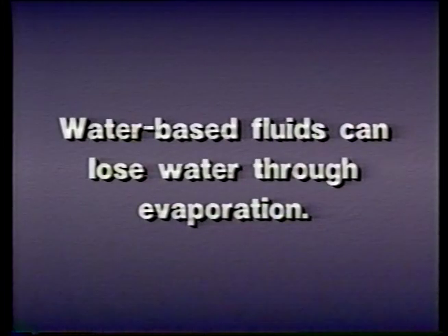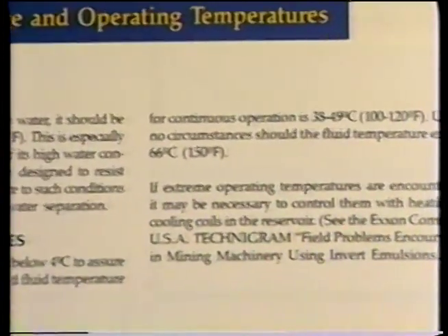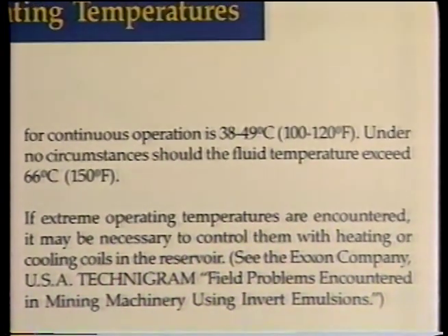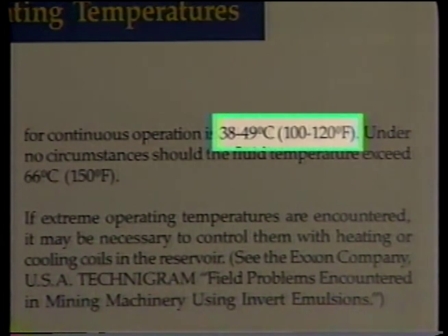A common disadvantage of all water-based fluids is their tendency to lose water through evaporation. That's why most water-based fluids are recommended for use at temperatures below 140 degrees Fahrenheit. 120 degrees is the most common recommended maximum.